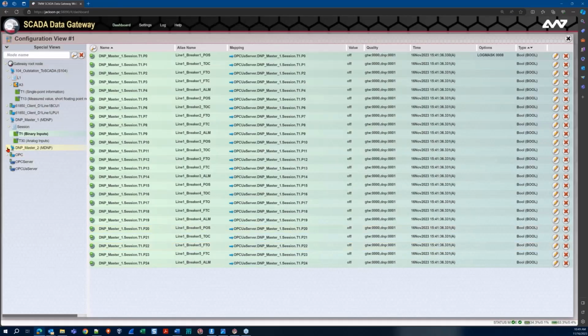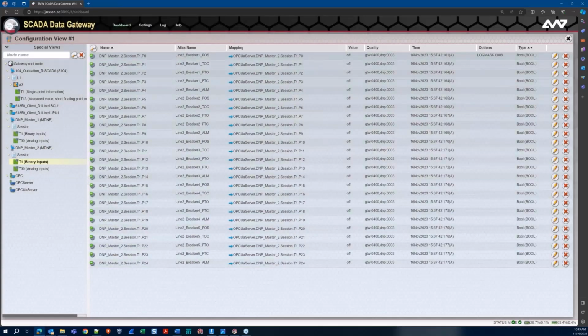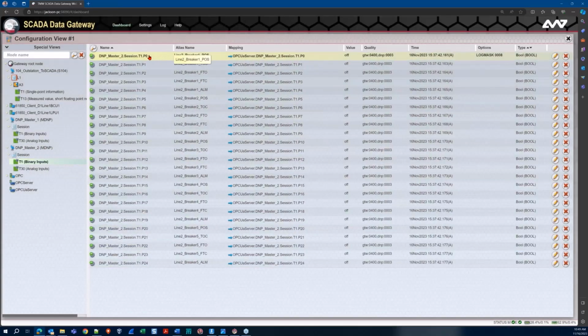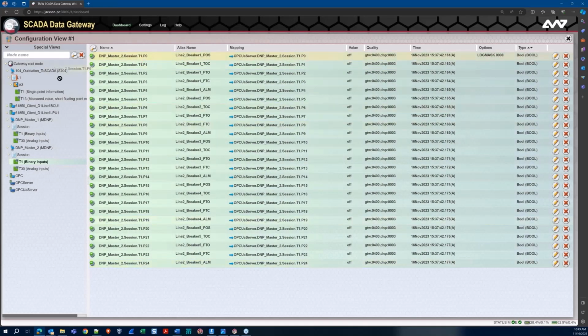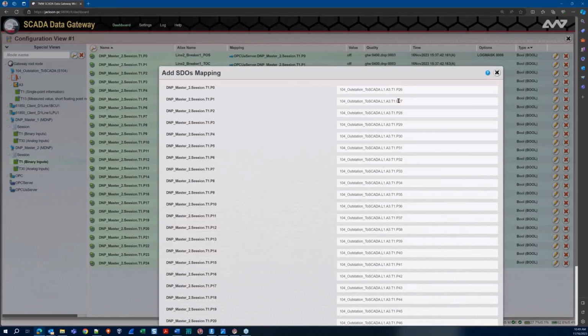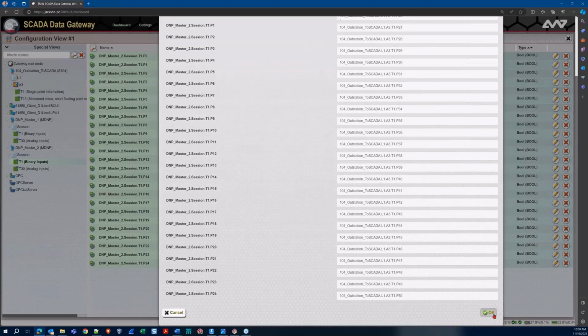Now I could do the same thing for DNP Master 2, take all of my binary inputs and map them up as well. Notice 1 through 25 were my initial 25 points, so the next available index is 26. My DNP Master session 2, T1 P0, which is my line 2 breaker position, is going to be mapped on the outgoing 104 side to P26 of the same type 1. Hit OK, and that's completed.